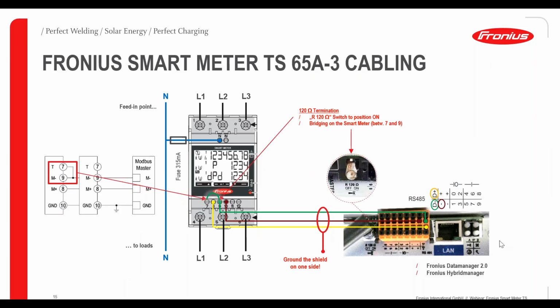Again, installation of the same smart meter, this time to the Snap inverter, to the data manager, not the new Gen 24. So of course, the installation on the smart meter side is exactly the same. But when it comes to the connection to the data manager, as we can see, we have the naming D minus, D plus, and minus for the ground. So again, from pin 8 we go to D plus, pin 9 to D minus, and we have the ground to minus the ground. And again, we use a shielded cable here, and we ground the shield.